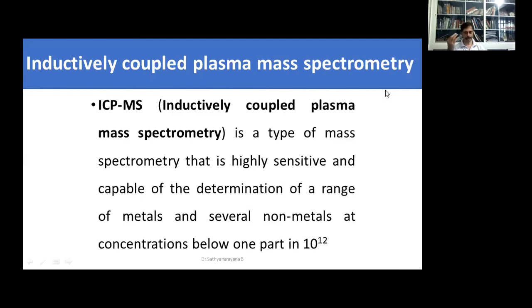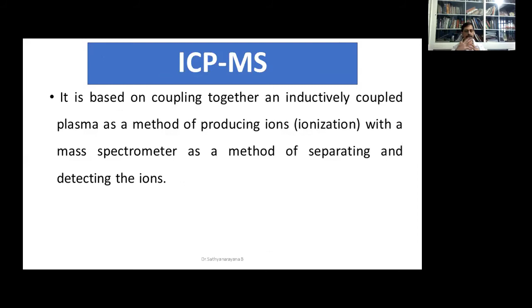It is based on coupling together an inductively coupled plasma as a method of producing ions or ionization, with a mass spectrometer as a method of separating and detecting the ions. You must be knowing by this time that a mass spectrometer separates the ions by mass to charge ratio. ICP-MS is also capable of monitoring isotopic speciation of the ions of choice.